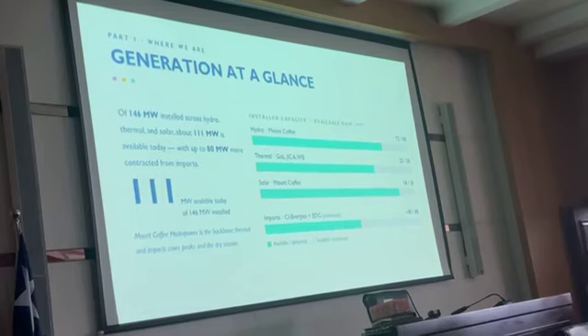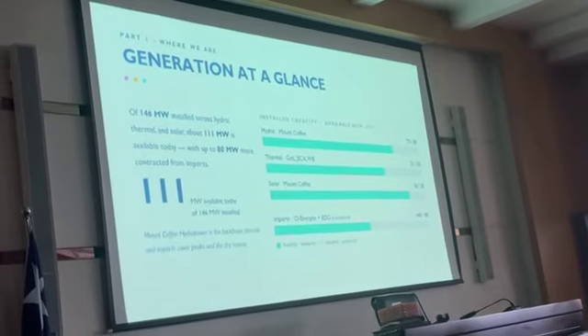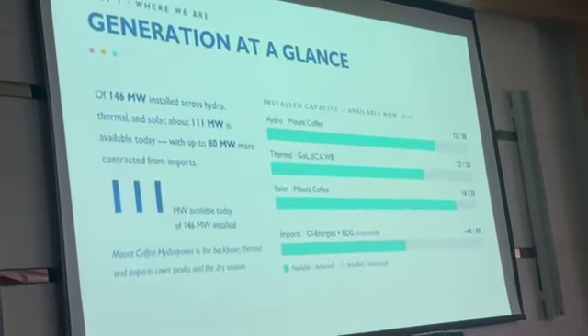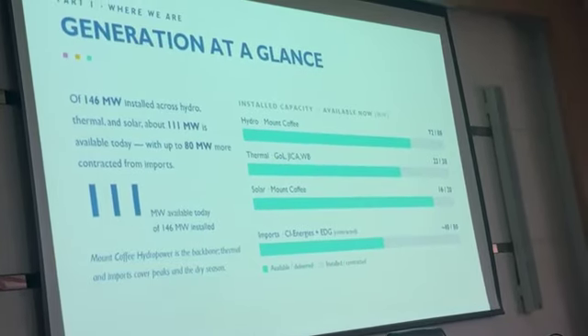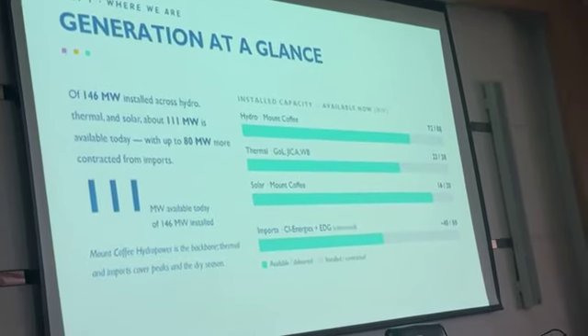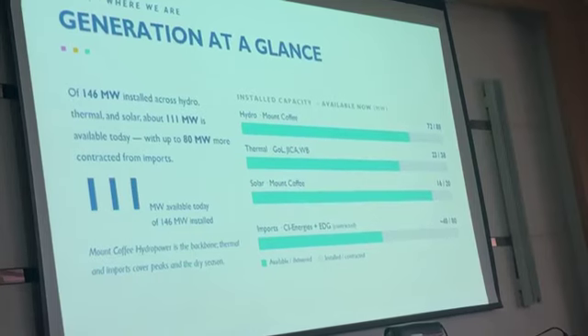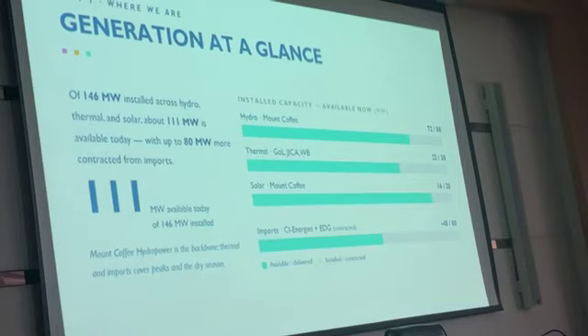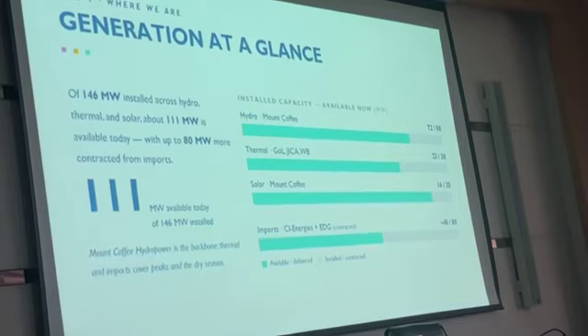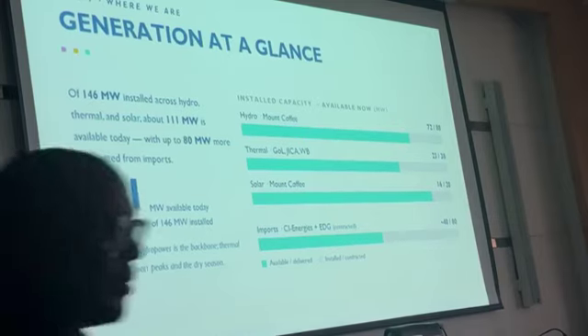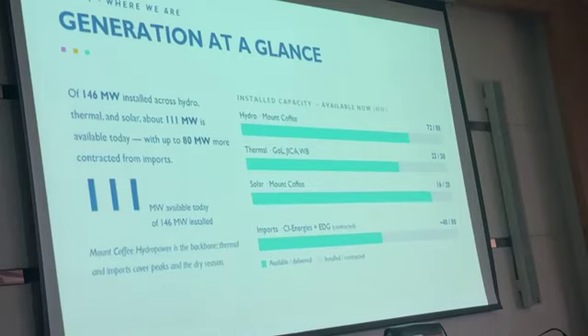Recently we dedicated the solar plant at Mount Coffee, 20 megawatts DC current, but the AC alternating current is 16 megawatts. Before it can be converted to AC, the losses we see are around 4 megawatts. So 16 is currently being injected into the grid.